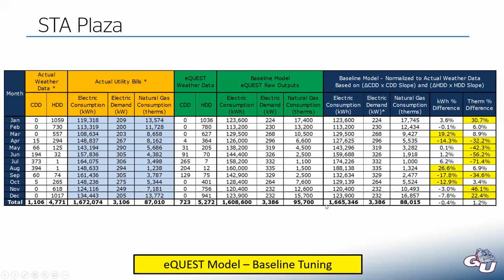And now our normalized values right here, you can see individual months are pretty far off on the electric and gas difference, but my overall for the year are within 1.5%, which I consider anything within 3 to 4% would be acceptable. So I would consider this a win. Even though some of my months, individual months, are pretty far off, my total over the year is still pretty close, extremely close. So that's creating the baseline. So now I have this version of a model that more or less mimics what is there today. And that's the hard part. That takes the bulk of the work.